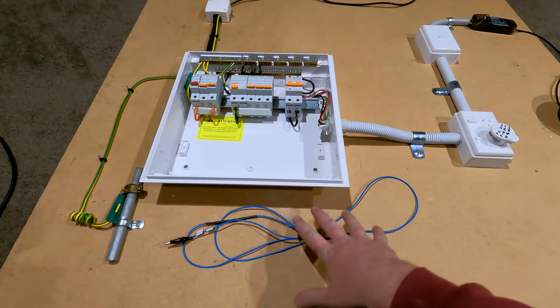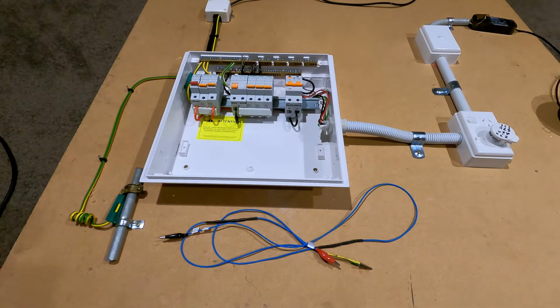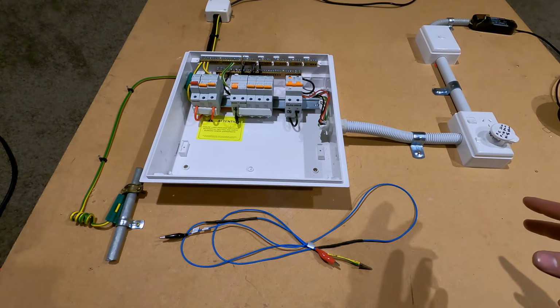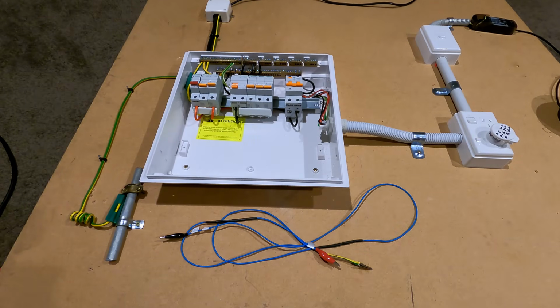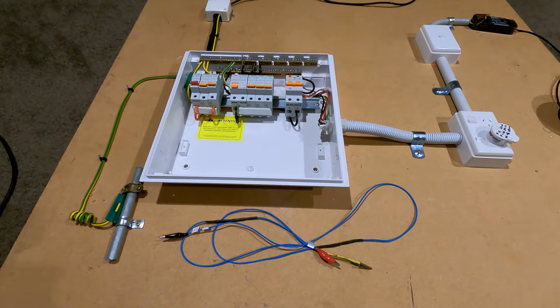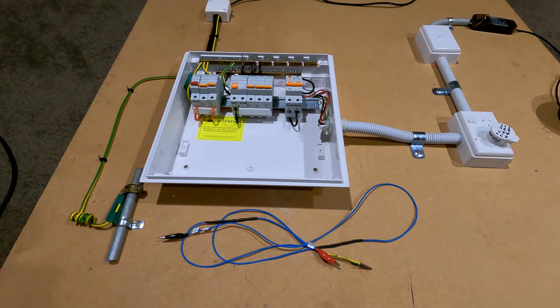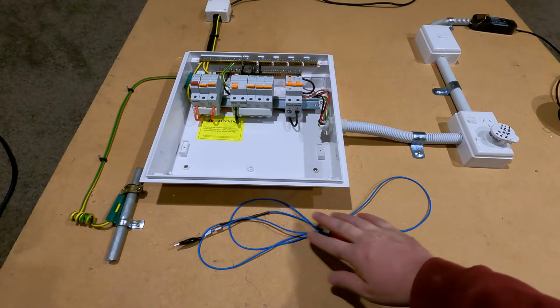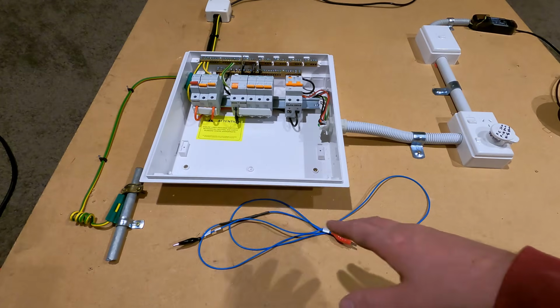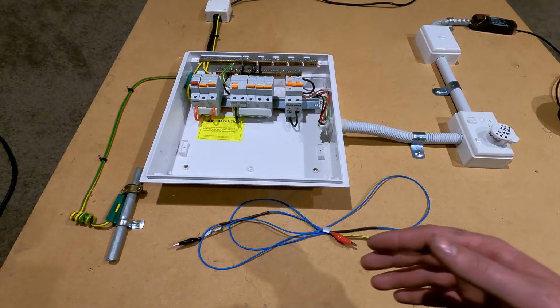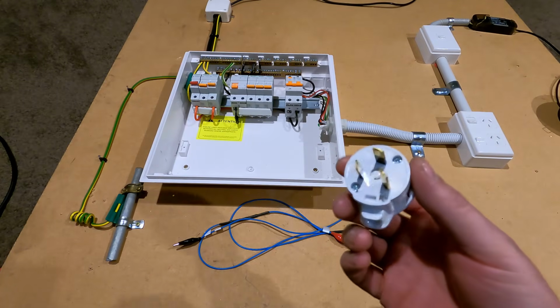Although I'm going to be showing you today using this on the switchboard and testing at the downlight, in reality that doesn't happen, mainly because the regs are more concerned with a shock hazard happening off a phase neutral transposition or metallic parts becoming live. There would be no shock hazard in a downlight should the phase neutral be transposed in it. The worst that would happen is it would stuff the driver, or if the earth was transposed, the fitting might not work. Now the other things that you should be testing with the likes of this is your fixed loads, so hot water cylinders, heaters, and other appliances that the standard socket doesn't actually fit into.